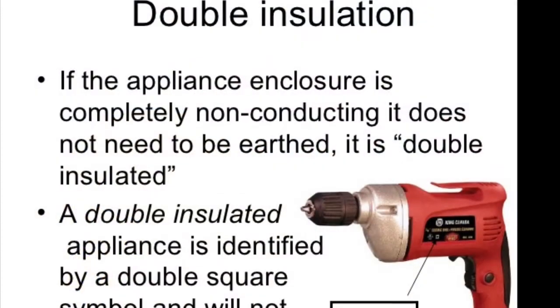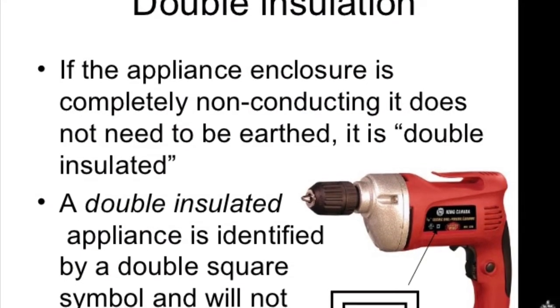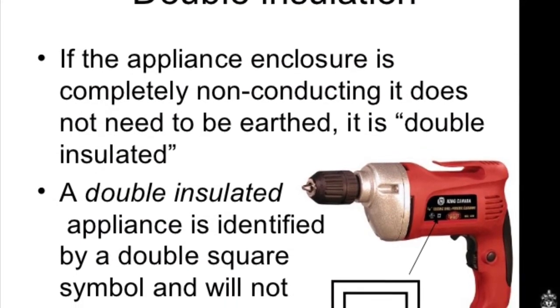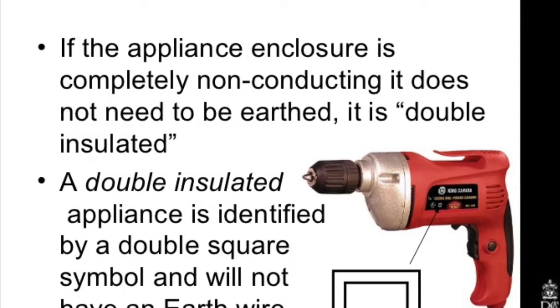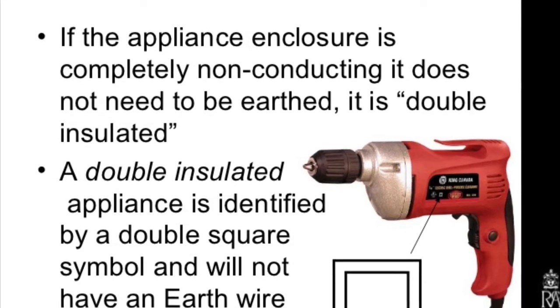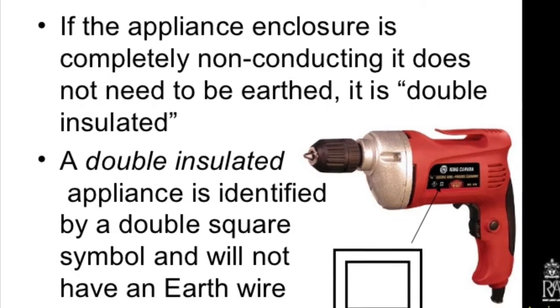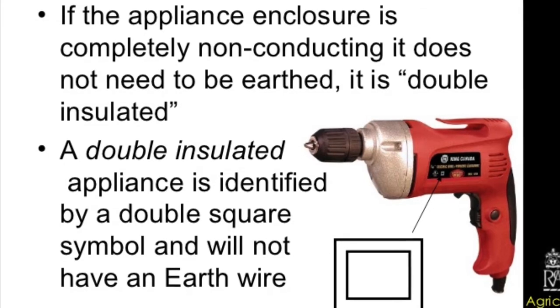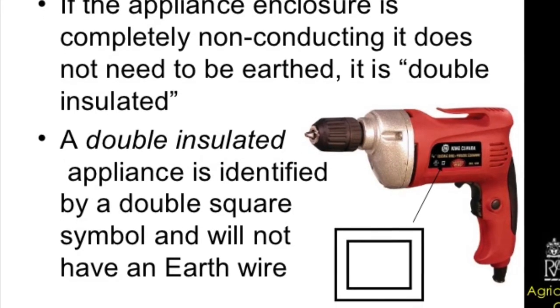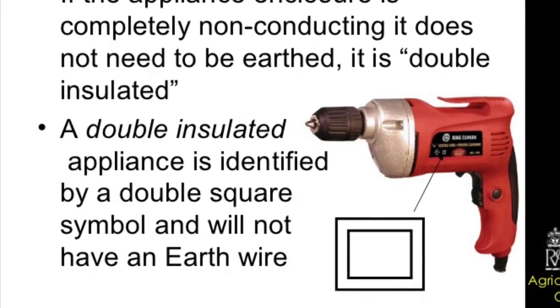For double insulated tools and equipment, visually inspect for external defects such as deformed or missing prongs, insulation damage, and indications of possible damage. If equipment is damaged or defective, let your supervisor or the safety director know. Remove the equipment from service so that nobody else uses the equipment.